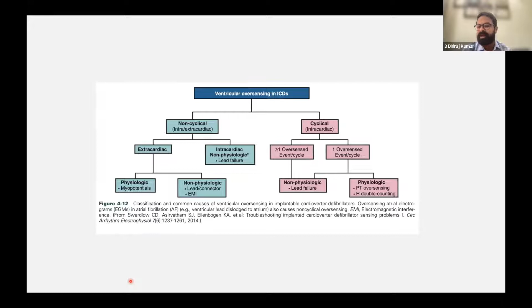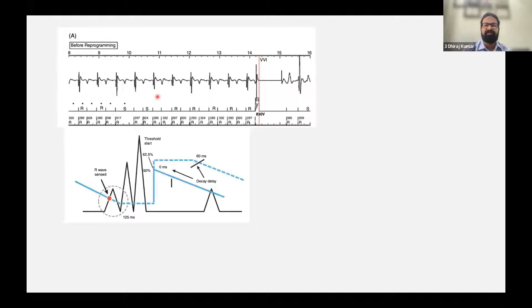So now this is an example that I found to be very interesting. Here, you see there is a near field signal, there's another signal, there's a near field signal, there's another signal. This second signal is coming with a little variation of 285 to 297 to 297. It's almost fixed. And the device interprets it as a tachycardia event and delivers a shock. Now, what is this signal? This is nothing but a T wave, a tallish T wave that the device is sensing. Why is it so? In ICDs, we don't have a fixed detection threshold. We have a detection threshold which starts high just after the QRS and then decays.